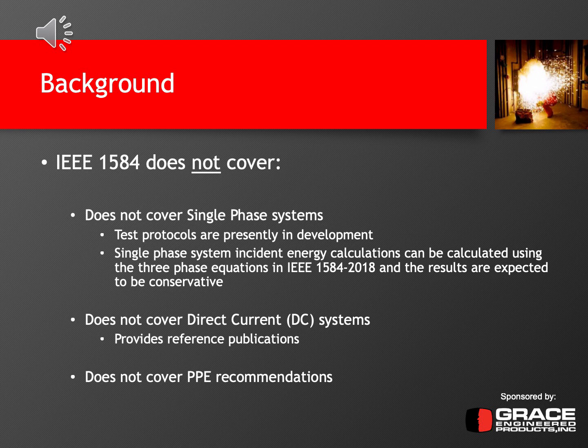But at the moment, the only guidance really on calculating the incident energy from single-phase systems that's presented in IEEE 1584 would be to use the three-phase equations, and basically the results of the three-phase equations are expected and anticipated to be conservative estimates and not more appropriate or more accurate estimates for single-phase systems in particular. However, that conservative estimate may require someone to wear a higher rated PPE or safety equipment than what would necessarily be needed if it was an actual single-phase calculation.